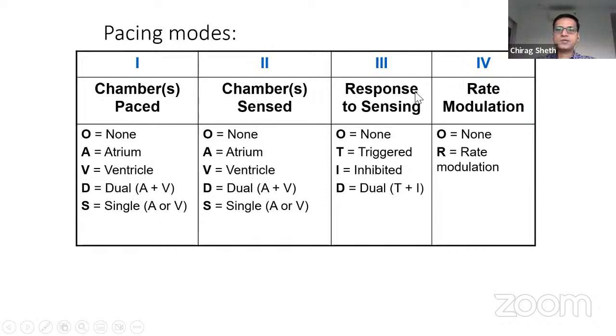The third letter denotes the response to sensing. So if I say DDD, that means it can have a dual response. If it senses that the native event is there, it will remain inhibited. And if the native event is not there, it will stimulate. So this is called response to sensing. And the fourth is a function called rate modulation. So if I say VVIR, that means it's a ventricular based pacemaker with rate modulation possible. If I say DDDR, it is a double chamber pacemaker with rate modulation possible. So this is in brief how the pacemaker modes are denoted.